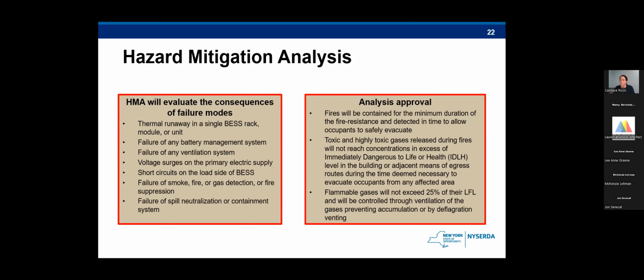And if you're familiar with our battery storage guidebook, this is also where we've gotten the threshold to differentiate between tier 1 and tier 2 systems. Anything over 600 kilowatt hours would be tier 2, and they would also have to go through this hazard mitigation analysis. So this study is done to evaluate the consequences of different failure modes. These are usually done by an engineering firm for the town to determine the best approach on how to handle a failure. The analysis will evaluate the consequences of the following failure modes.